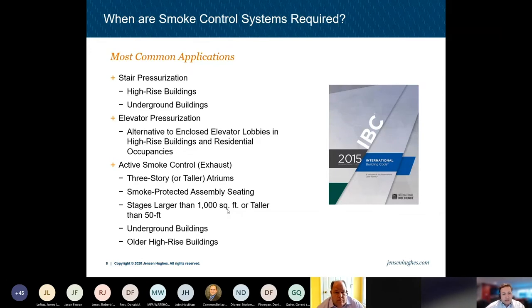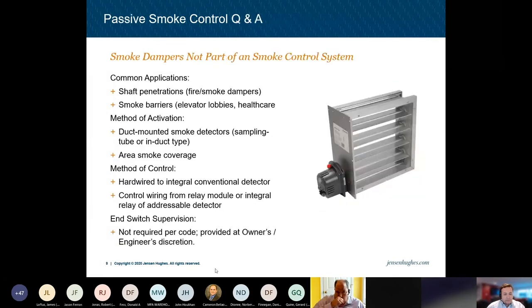Elevator pressurization, you typically see that in high-rise buildings as an alternative to enclosed elevator lobbies, but you also could see it in residential low-rise occupancies. And then there's the active smoke control systems. Those are the ones that people typically think of when they hear smoke control, and that's 3-story or taller atriums, smoke-protected assembly seating, stages over 1,000 square feet or taller than 50 feet, underground buildings, and then older high-rise buildings, especially in Massachusetts. Additional systems could exist as a result of older code requirements, such as vestibule ventilation, stairwell exhaust, and sandwich systems. But typically you see the newer systems in new construction, which is where you'll find the majority of these.